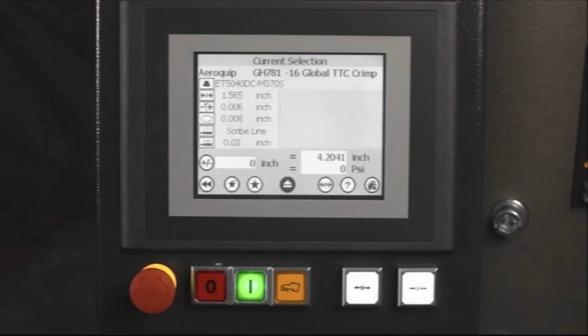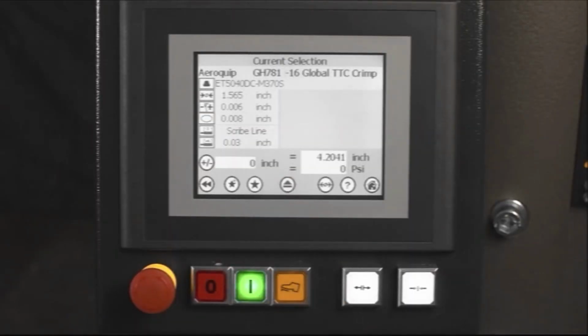To set the ET5050 to open the tooling automatically after crimping, touch the triangle icon. A green triangle notifies operators of an auto-retracting of crimper head. If the button is red and white, the operator will have to press and hold the retract button until the assembly is free to move.